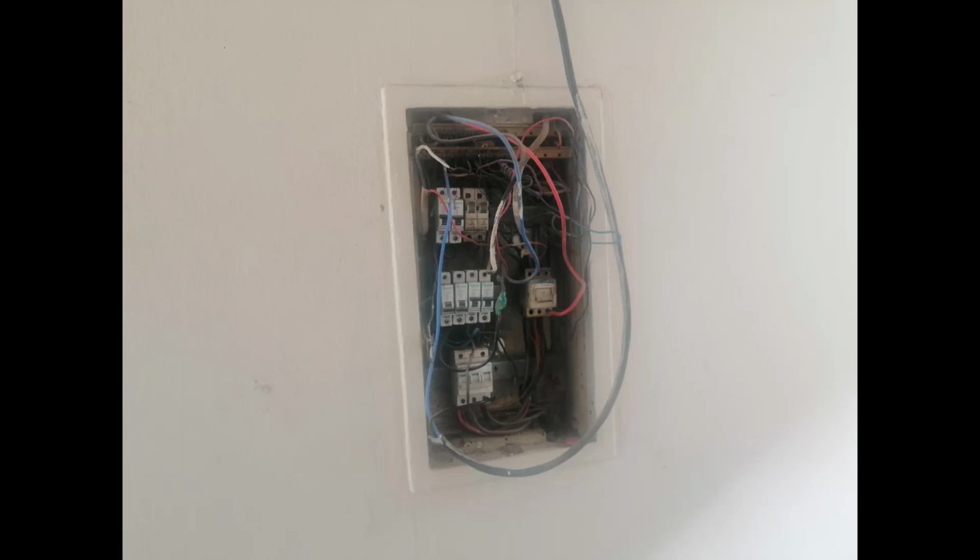So they were not really using the functionality of the circuit breaker. If a current that was too high came into the line, the circuit breaker was not going to trip off, because they were not actually using its functionality. They just put a cable in one side of the circuit breaker and looped it that way. So those circuit breakers were not performing their function. What we did was replace those damaged and old circuit breakers with new ones, so each of the lines connected to that building had its own separate circuit breaker, taking in current and supplying the load in that distribution board.